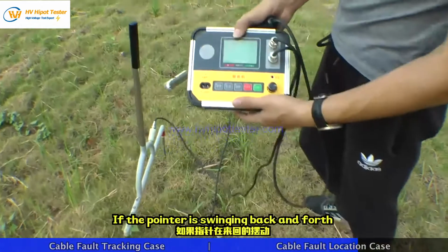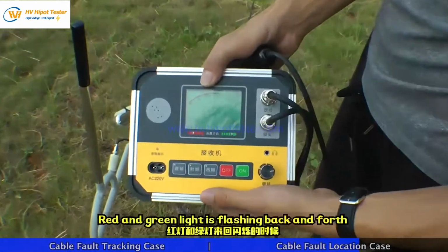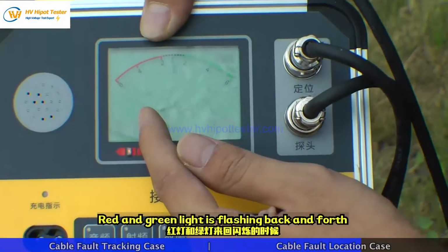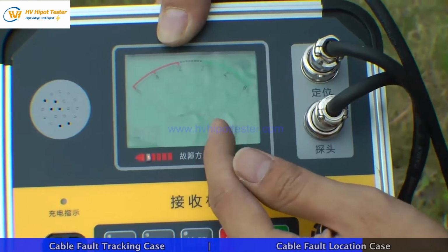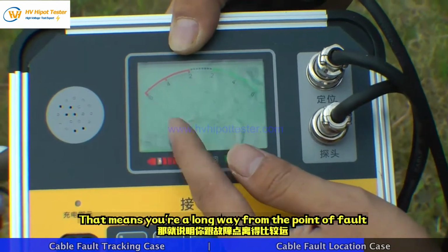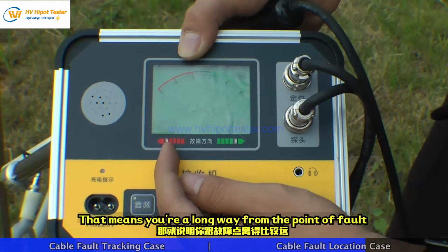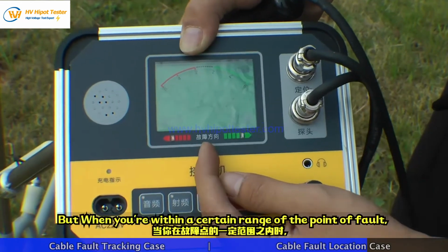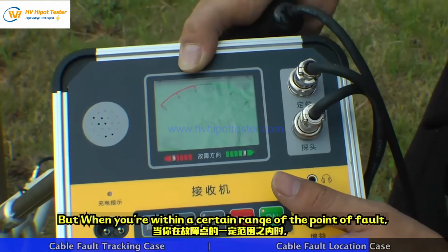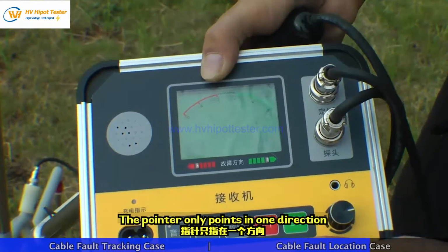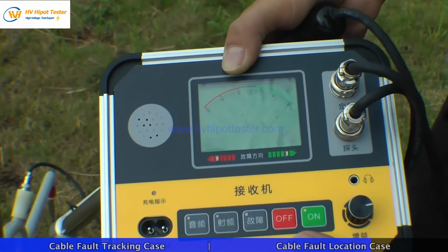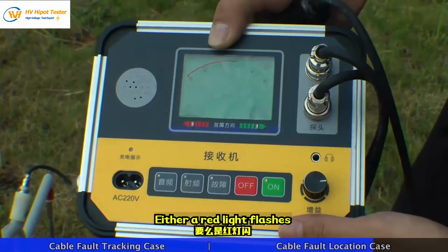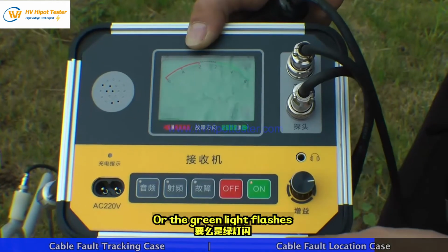One more point to clarify. If the pointer is swinging back and forth, red and green light is flashing back and forth. That means you are a long way from the point of fault. But when you are within a certain range of the point of fault, the pointer only points in one direction, either a red light flashes or the green light flashes.